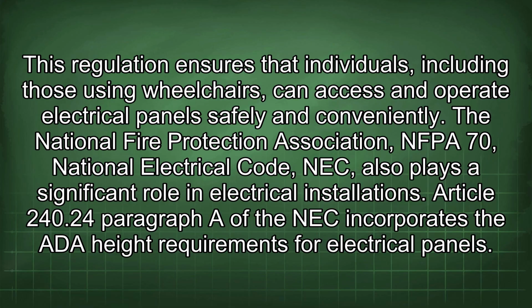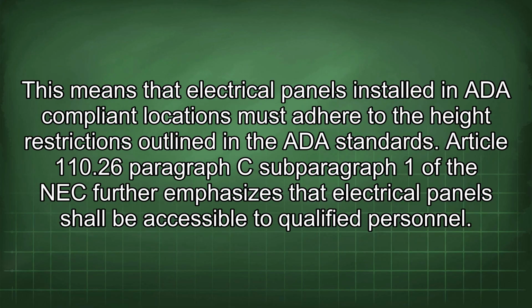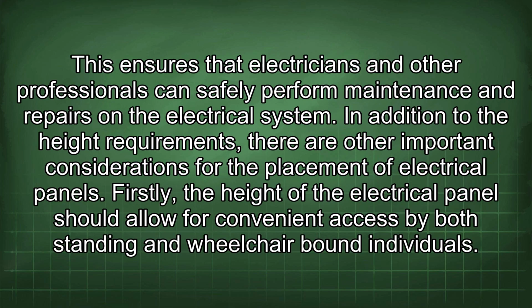The National Fire Protection Association, NFPA 70, National Electrical Code, NEC, also plays a significant role in electrical installations. Article 240.24 paragraph A of the NEC incorporates the ADA height requirements for electrical panels. This means that electrical panels installed in ADA-compliant locations must adhere to the height restrictions outlined in the ADA standards. Article 110.26 paragraph C subparagraph 1 of the NEC further emphasizes that electrical panels shall be accessible to qualified personnel. This ensures that electricians and other professionals can safely perform maintenance and repairs on the electrical system.